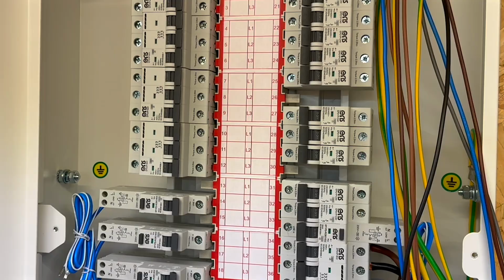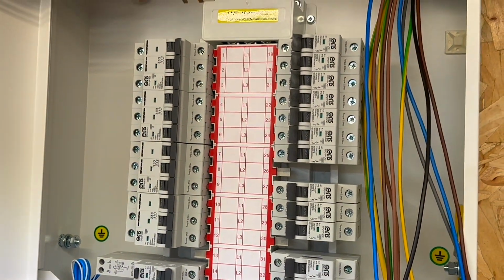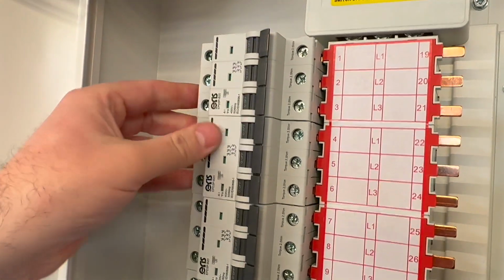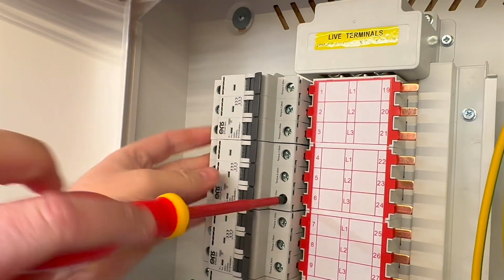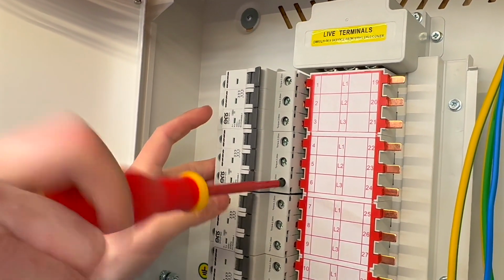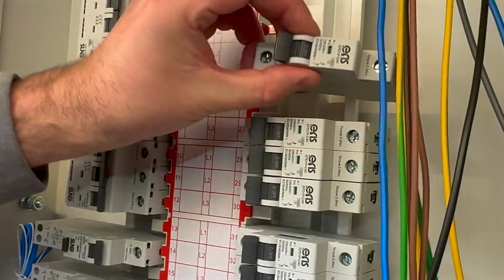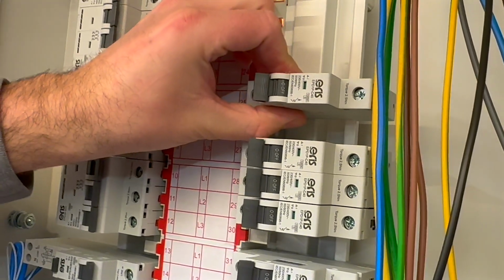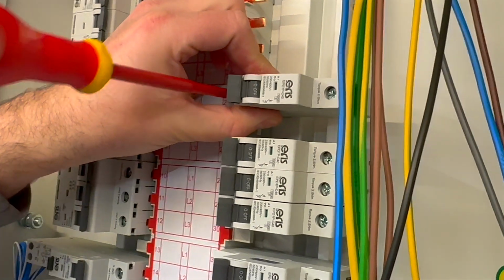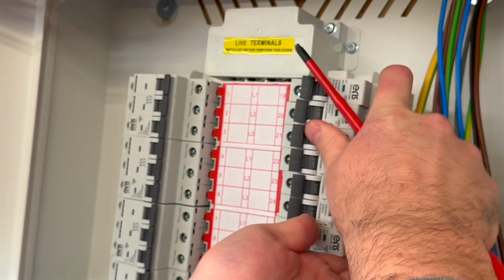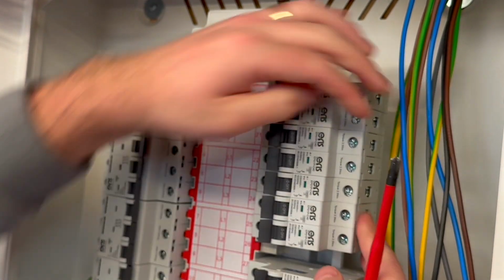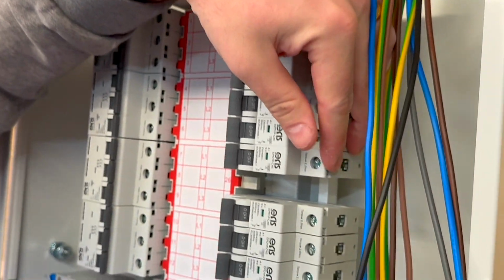One of the main distinctions is how the size of the board is specified. For example, this is a 12-way board, meaning it can support 12 outgoing 3-phase circuits. However, despite having a 3-phase input, it can also supply single-phase circuits. When used for single-phase circuits, it can accommodate up to 36 outgoing circuits, offering greater versatility, and of course it can be a combination of 3-phase and single-phase circuits.